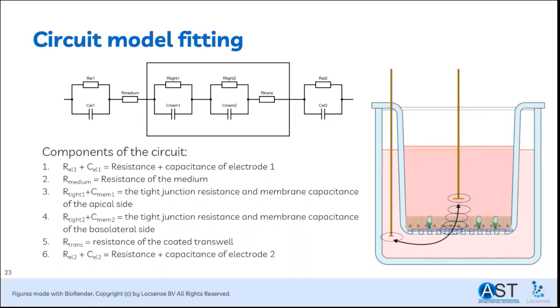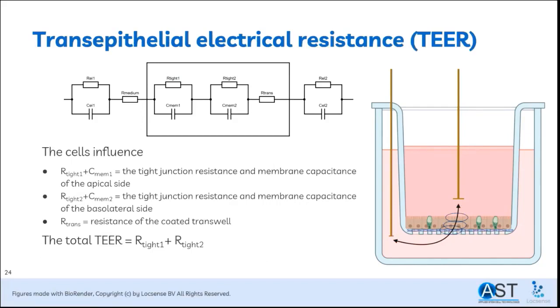Now we have the whole circuit with all its components. Zooming in on the impedance caused by the cells, we see two RC circuits and a cell-transwell interface. The choice for each RC circuit is to either go through the cell membrane (the capacitors) or the tight junctions (the resistors). The total TEER is the sum of the apical tight junction resistance and the basolateral tight junction resistance. With circuit model fitting and full-spectrum impedance results, you can assign a value to each component and thereby find the TEER.